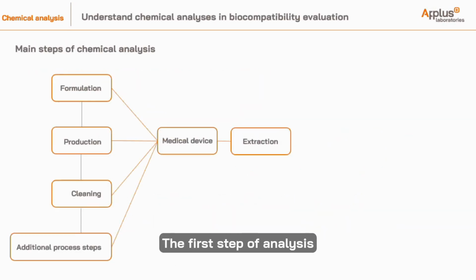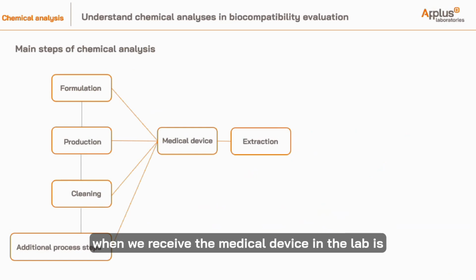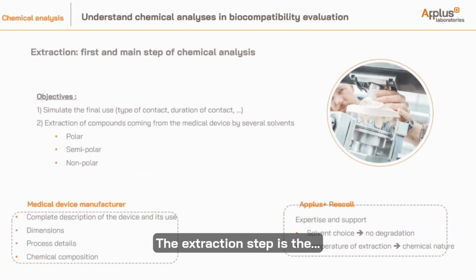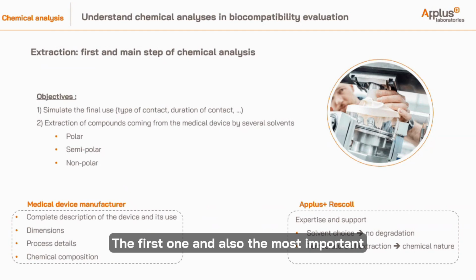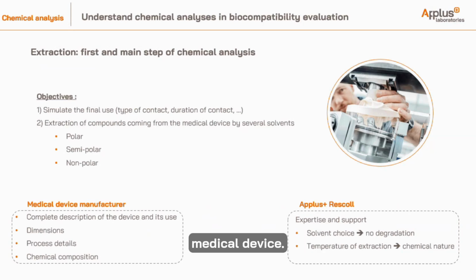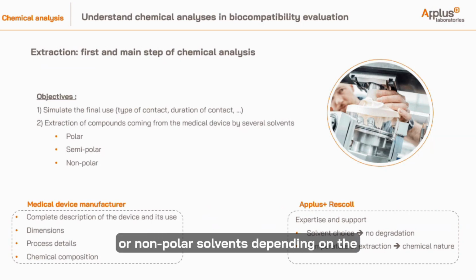The first step of analysis when we receive the medical device in the lab is to perform extraction. The extraction step is the first one and also the most important part of the chemical analysis. The objective of this step is to extract compounds from the medical device. The medical device most often is a solid product, and compounds can be on the surface of the medical device, but can also be trapped in the medical device. So we have to use solvents that can be polar solvents, semi-polar solvents, or non-polar solvents, depending on the use of the medical device.